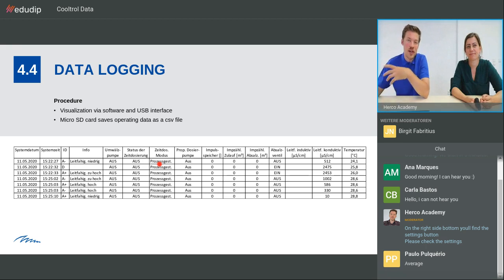This is a really huge difference to the old Cooltrol, because it's now not called manual or automatic or anything. It's called process controlled or on and off. So it's basically only those three left now. This is also for a better understanding, so it's easier to handle for the customers. Then we also have the proportional dosing, only the state on or off, then the impulses of the flow meters for the different ones, feed, the drain, and also here the state of the blowdown valve, then the conductivity, inductive or conductive, whichever probe is connected, and then the temperature of the system. So it gives you all the information you actually need from the system.